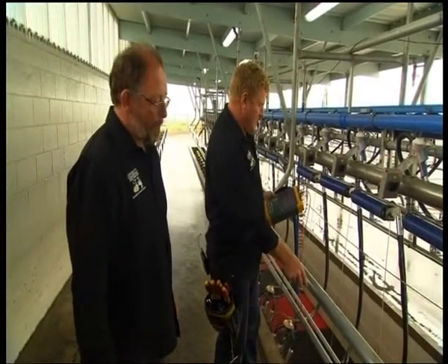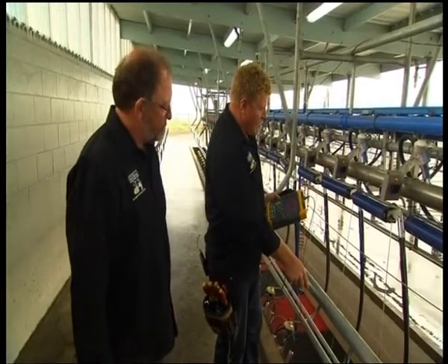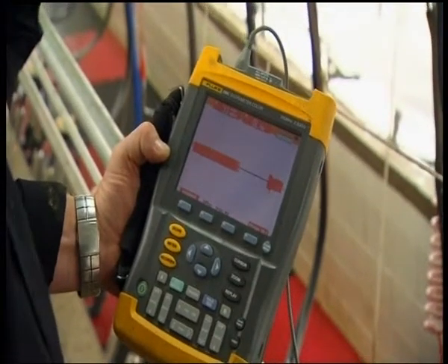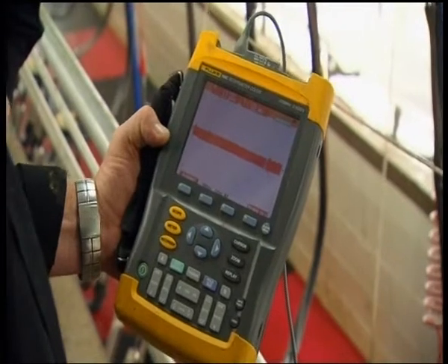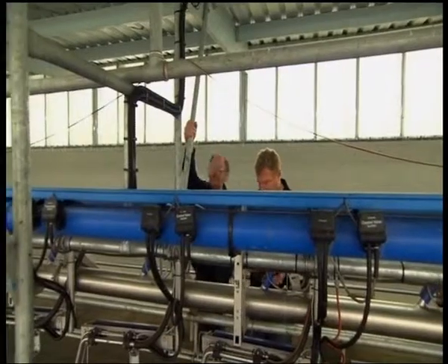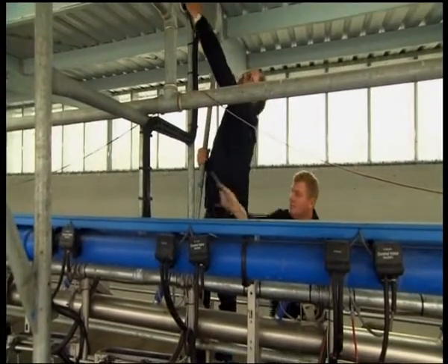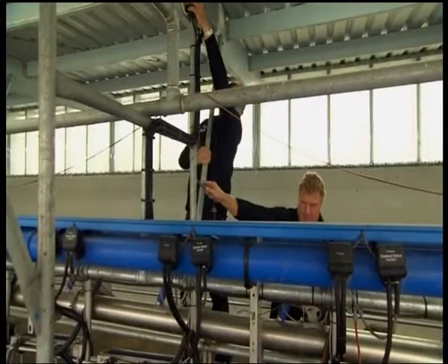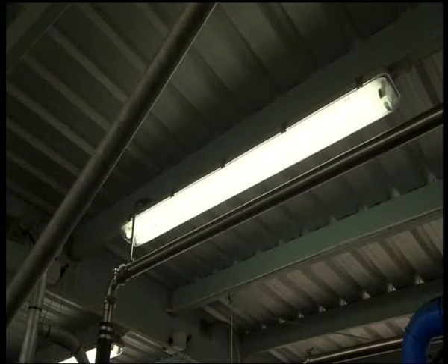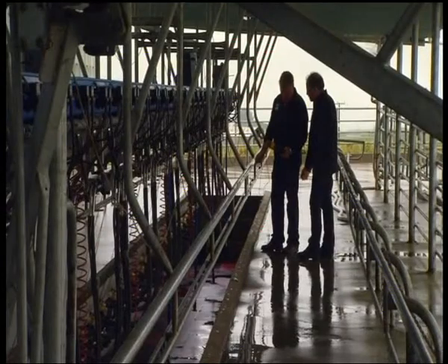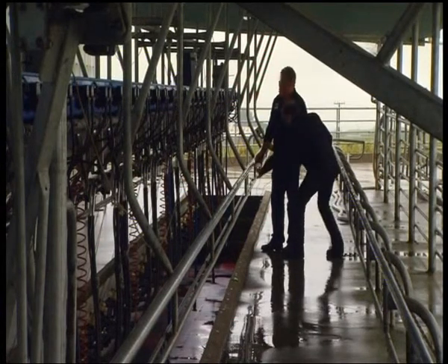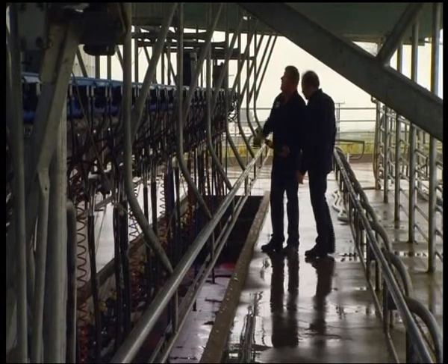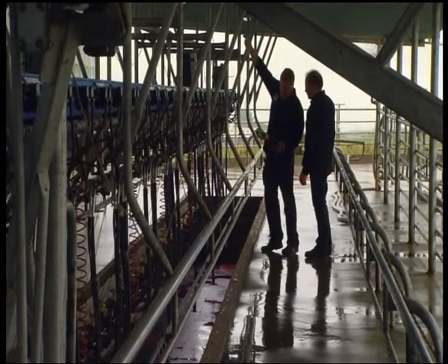Yep. This unit that I'm using is a scope meter, and it'll measure EMC voltage. It's a very fine unit. They're $10,000 a piece. We've actually got 3 in our company, and I think there's only another couple around in the country, so there's probably only 4 or 5 in New Zealand. Essential because it's an indicative reading of what's going on, and I can do it quickly, walk around the shed and pinpoint and see exactly where the EMC voltage is.